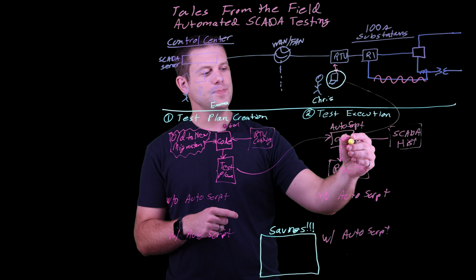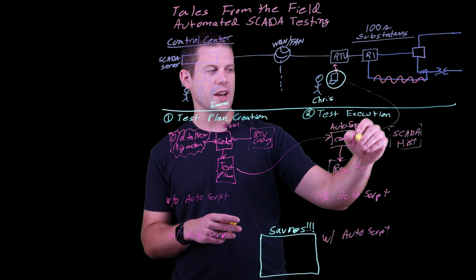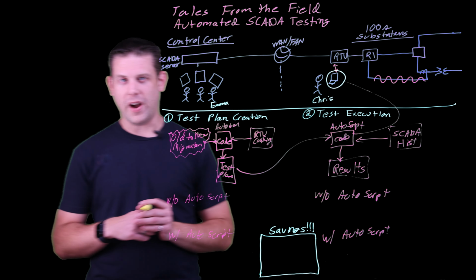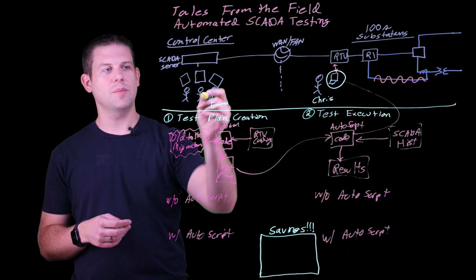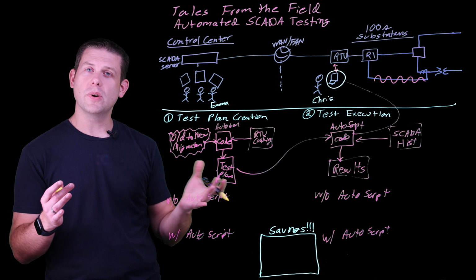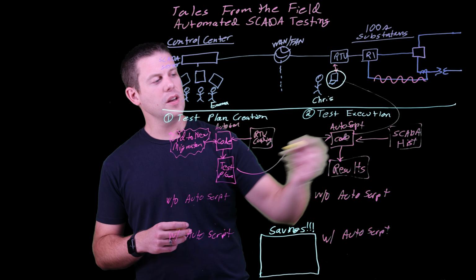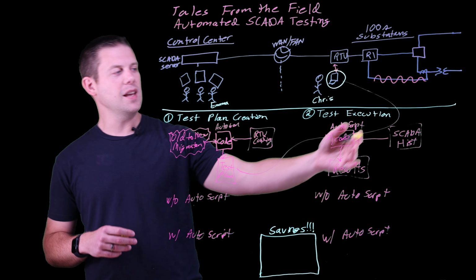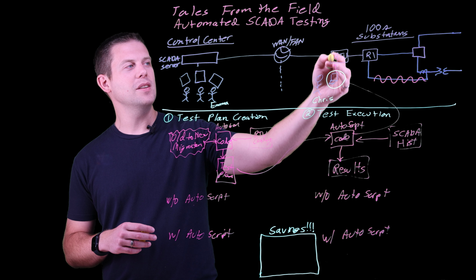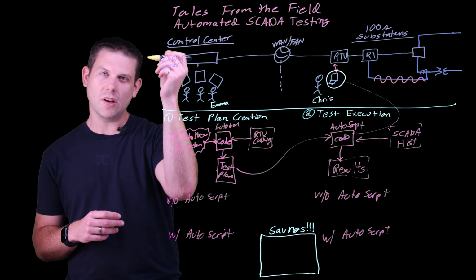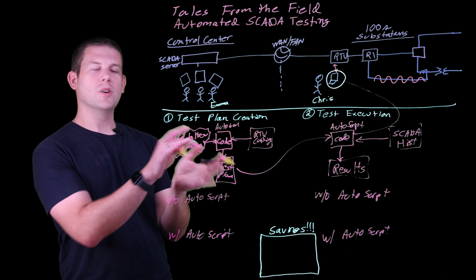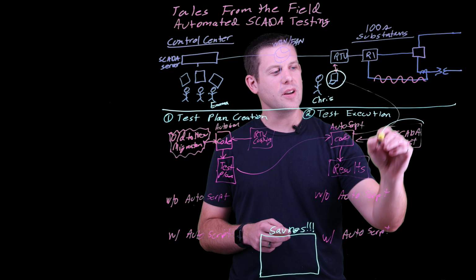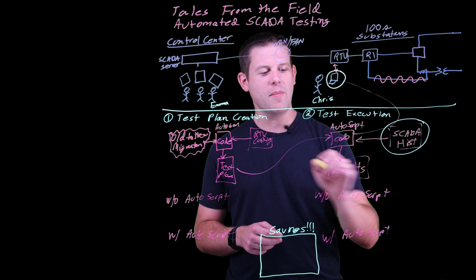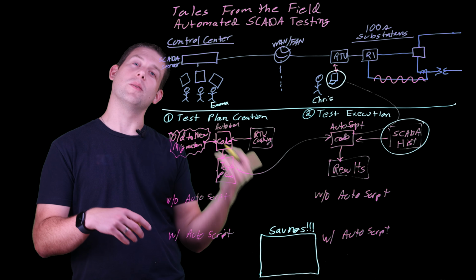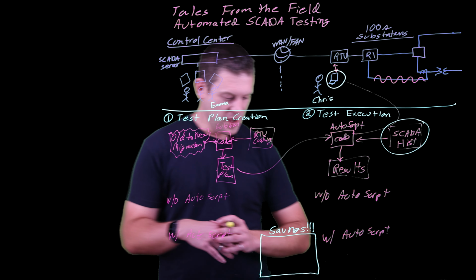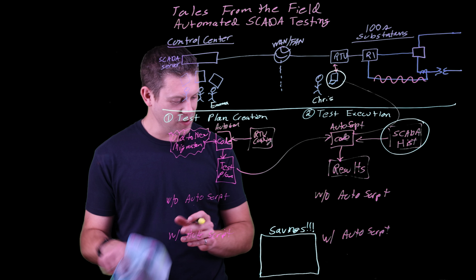The code also took in, for execution, the SCADA historian file. As I mentioned, traditionally Chris is forcing values and asking Emma what she saw. Our software running on the laptop was able to take in the historian data as it's hooked in, force all these points one after another, then load up the historian file and automatically produce results - did the point pass, did it fail, was the scaling off? The savings here were phenomenal.